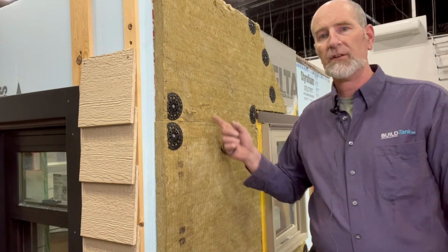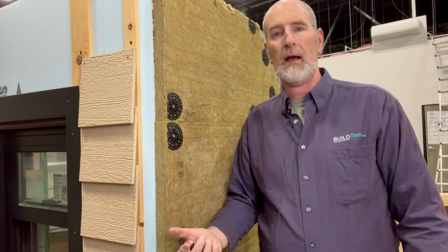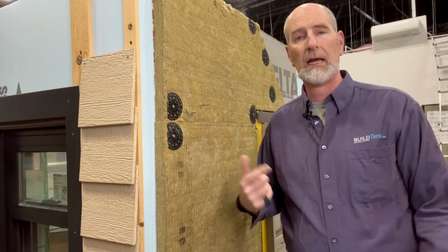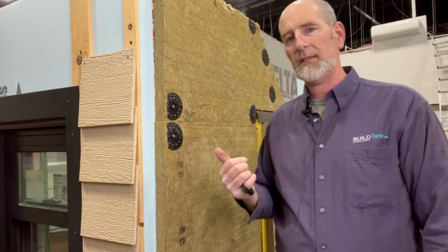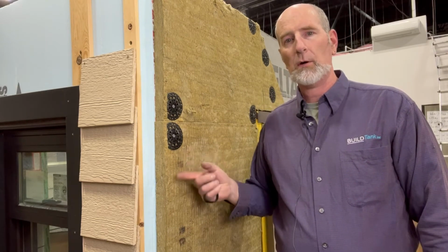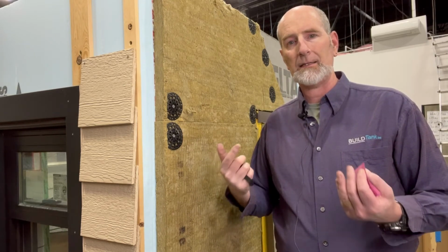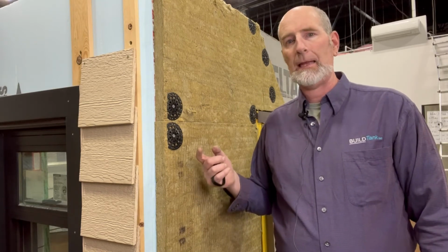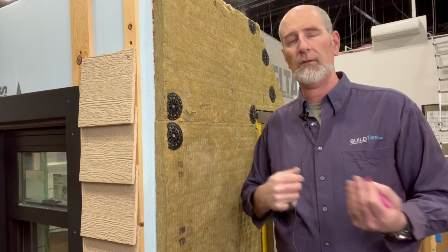And if I raise the surface temperature by putting continuous insulation on the outside, then I'm going to keep it in its vapor state, and I'm going to have the ability for that assembly to dry, which gets us to our next point, the drying potential of the assembly. Now, the drying potential of the assembly is created by a couple things. One is, what is the permeability of all the materials that are creating that assembly, and which one has the least permeability, the ability for moisture to diffuse through that material, and how am I going to overcome it so that I have at least good drying potential in one of those directions.